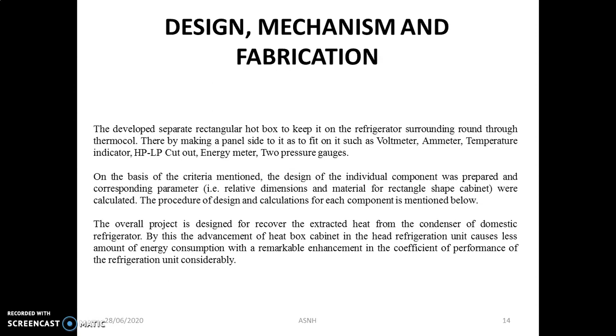Besides that, there is also a huge opportunity in waste heat recovery from the condenser side for water warming applications. Instead of keeping the hot box, we insert the condenser coil in normal water. The main function of the condenser is to reject heat, and instead of rejecting heat to the atmosphere, the coil rejects heat to the water, and the water gets heated to about 45 to 50 degrees centigrade. We can utilize this water for dish cleaning applications, or as hot water in kitchen applications. So these are some opportunities of waste heat recovery.